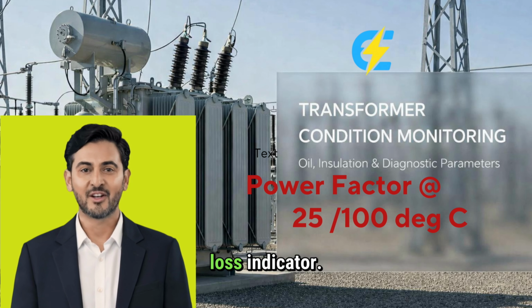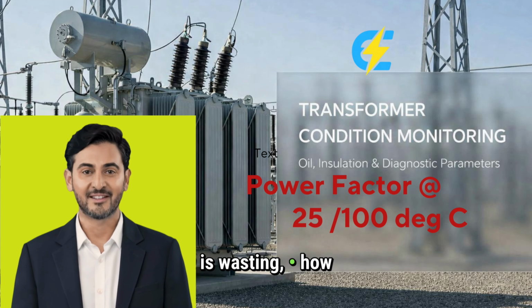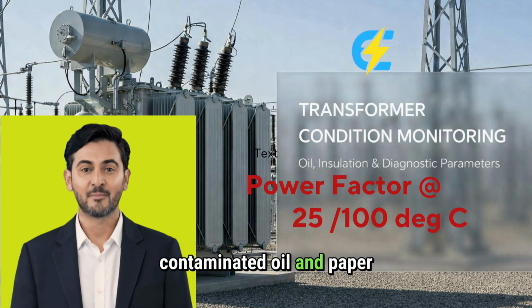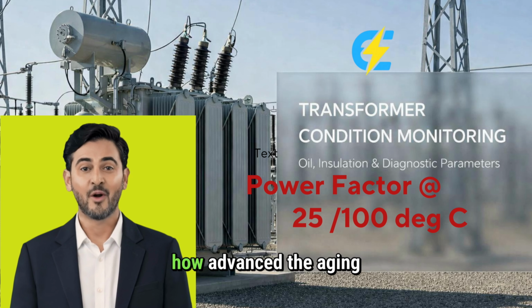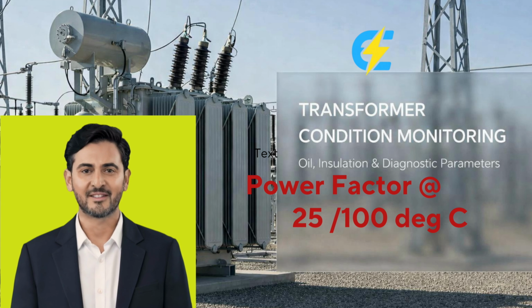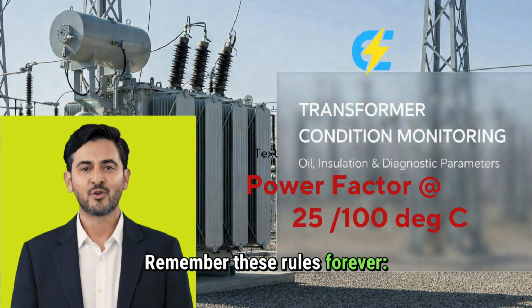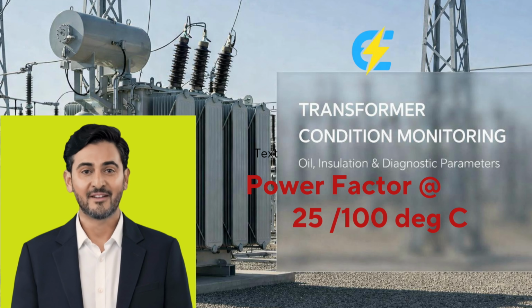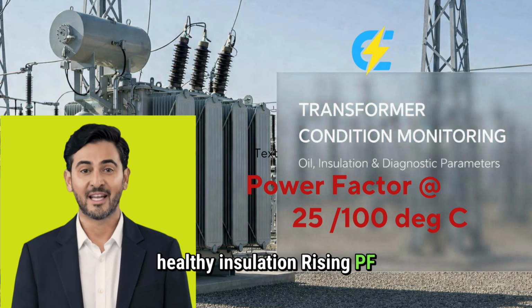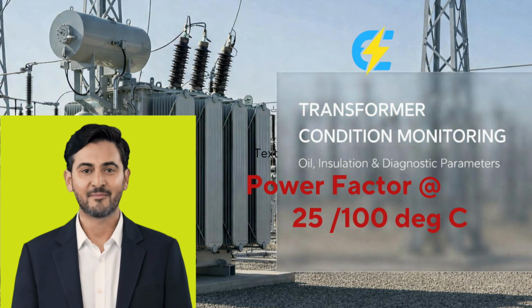Power factor is a loss indicator. It tells you how much energy insulation is wasting, how contaminated oil and paper have become, and how advanced the aging process is. Remember these rules forever. Low PF, clean, healthy insulation. Rising PF, contamination or aging. High PF, insulation degradation risk.